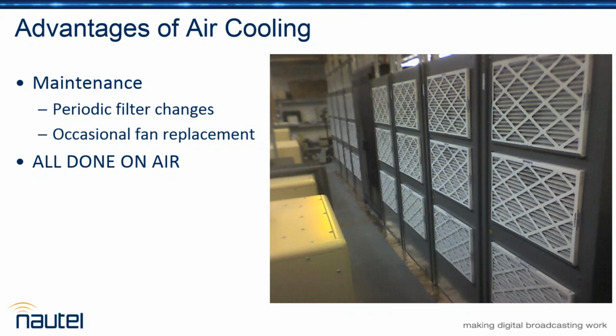Whereas in a liquid-cooled system, if you need to change the filter, which does need to be done after an initial run time, and then typically every couple or 5 years after that, you've got to be able to bypass that filter, take it out without spilling anything, swap in the new one, and it does take a little more time and a little more care. Absolutely. So it requires a lot more training and experience than, hey, go out to the transmitter, yank the filter off the back, and slam this new one on.